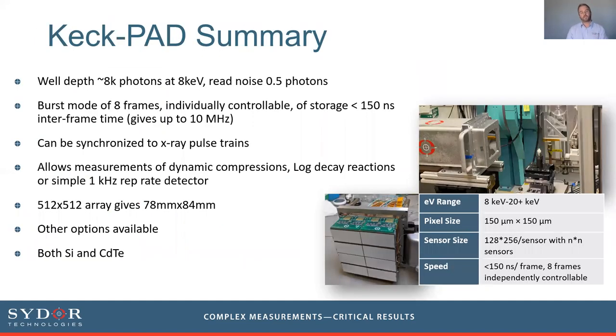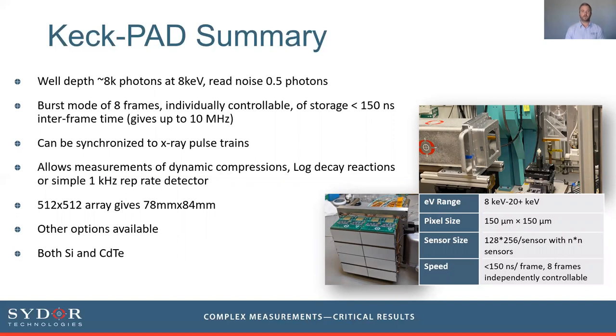In summary, the detector has a well depth of about 8,000 photons at 8 keV, giving a very good full-well capacity that can be adjusted with the gain settings to allow different full-well capacities. The read noise is about half a photon, so it remains very sensitive to the very low light levels encountered at these megahertz rates.